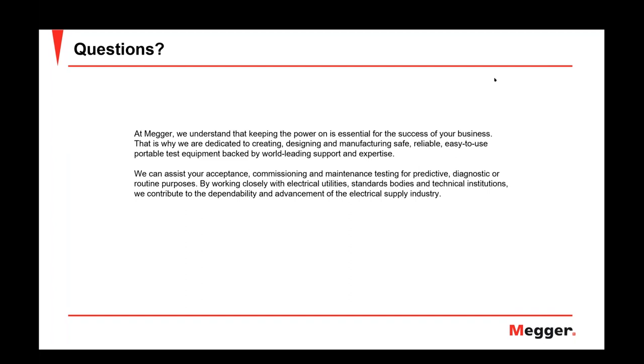Hi, thanks, Mike. Well, when the CT saturates in the protection system, what you have is the wrong image of the primary current on the secondary of the CT, which means that the relay that's using that secondary value to provide a current measurement is going to provide wrong measurements in both the magnitude and the phase angle. Since both are affected by the saturation of the CT, then we're going to have problems.